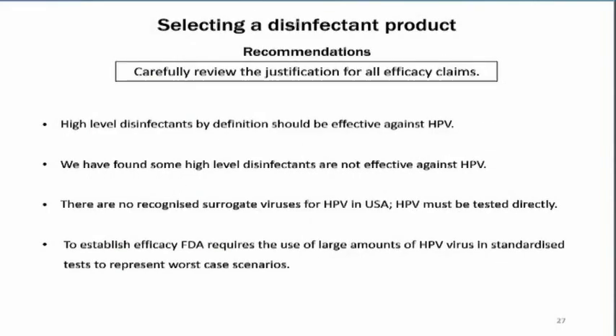So selecting a disinfectant product. Well, recommendations: you need to carefully review the justification for all efficacy claims. High-level disinfectants, by definition, should be effective against HPV. But we have found that some high-level disinfectants are not effective against HPV. There are no recognized surrogate viruses for HPV in the USA. HPV must be tested directly if you are to say that your disinfectant is effective against killing it. To establish efficacy, the FDA requires the use of large amounts of HPV virus in standardized tests to represent the worst-case scenarios.